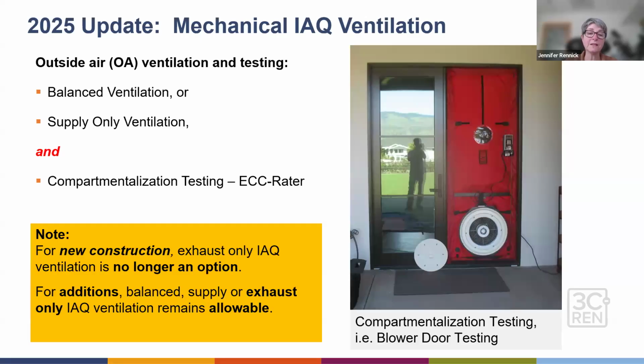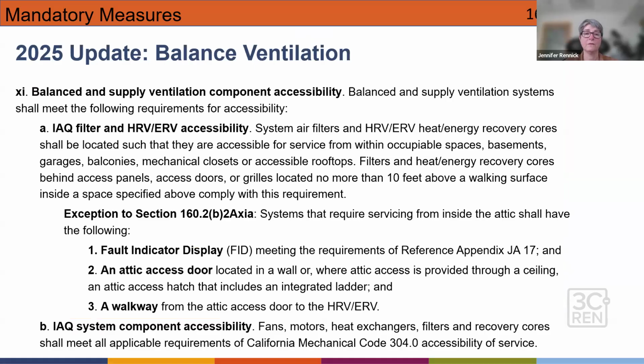Now, if you're doing additions or you're doing alterations, you can still do an exhaust only IAQ ventilation fan. But there's some caveats with the alterations. It depends on what you're doing. So with the code now, it reads for the balanced ventilation. This is the new part of it for the IAQ. So balanced supply ventilation component accessibility. So both balanced and supply, not exhaust only.